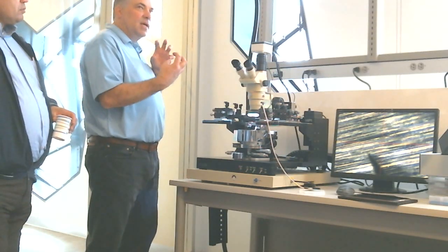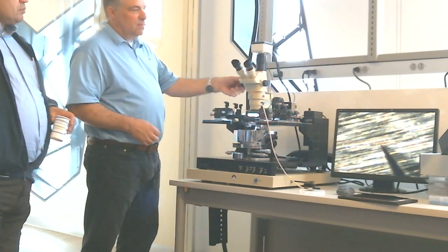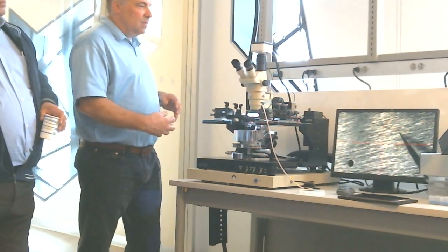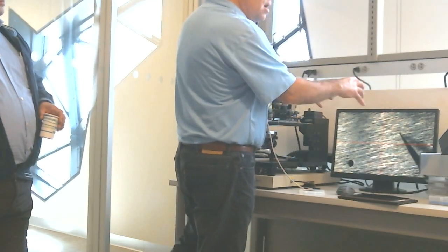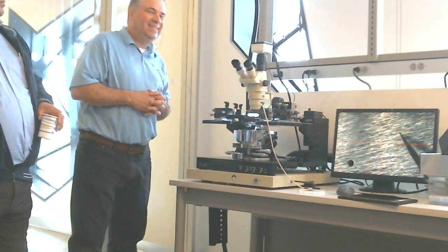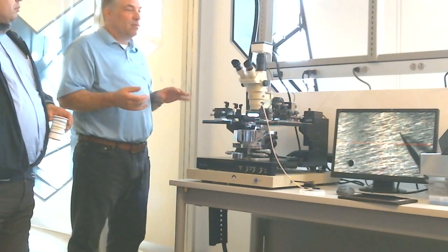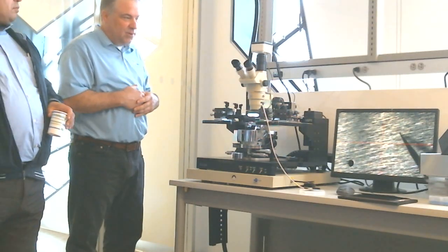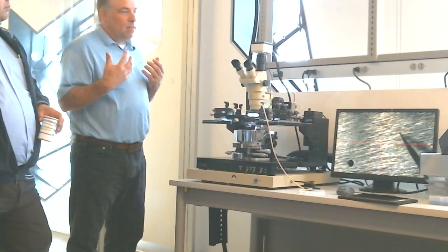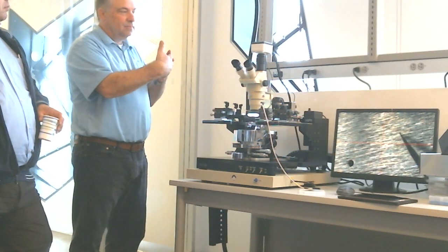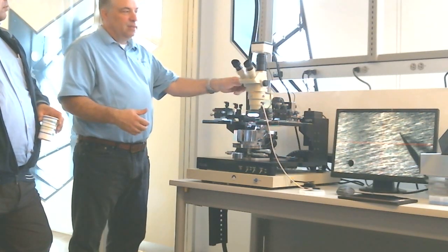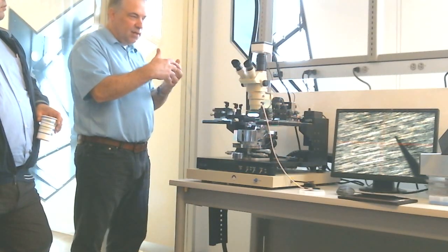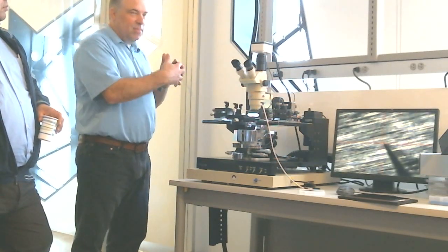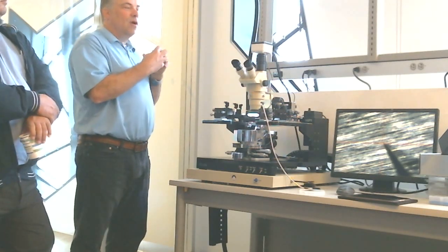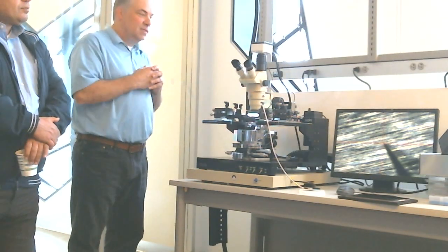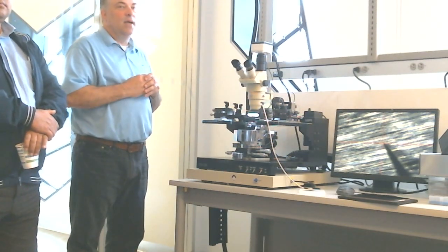And the first thing you want to do is take all your probes and move them into the field of view. You zoom out, and then you get all your probes, 3, 4, or 5, all within the view of the camera. It takes a little bit longer. Take your time. Don't try to rush through it or do it quick. It's too easy to make a mistake. But what you'll do is bring them into the view, and you'll gradually be dropping them down, bringing them closer, dropping them down, and bringing them closer. Basically repeating this process that I just did for all probes until you have all 4, 5, 6 probes touching the surface at the same time.